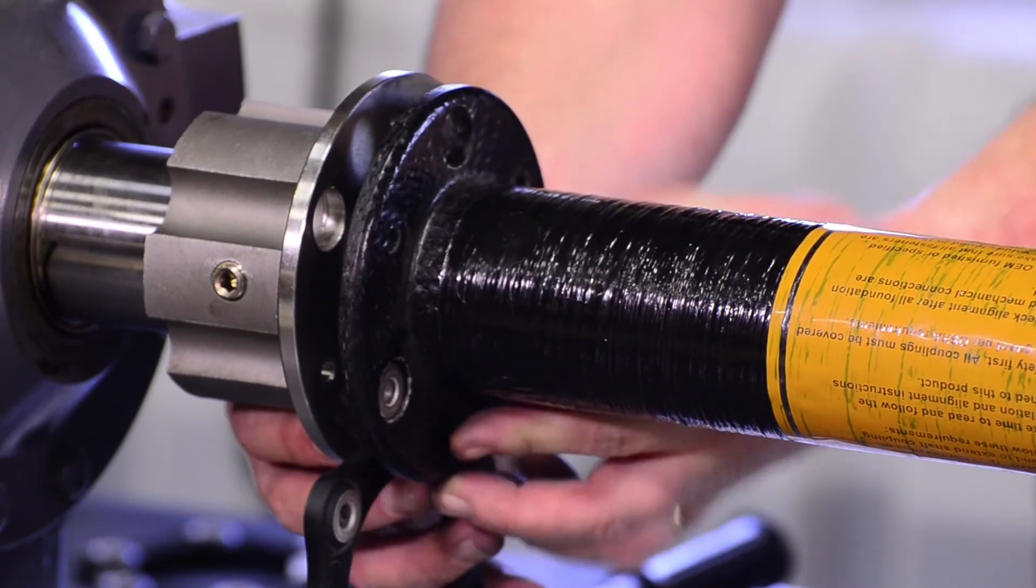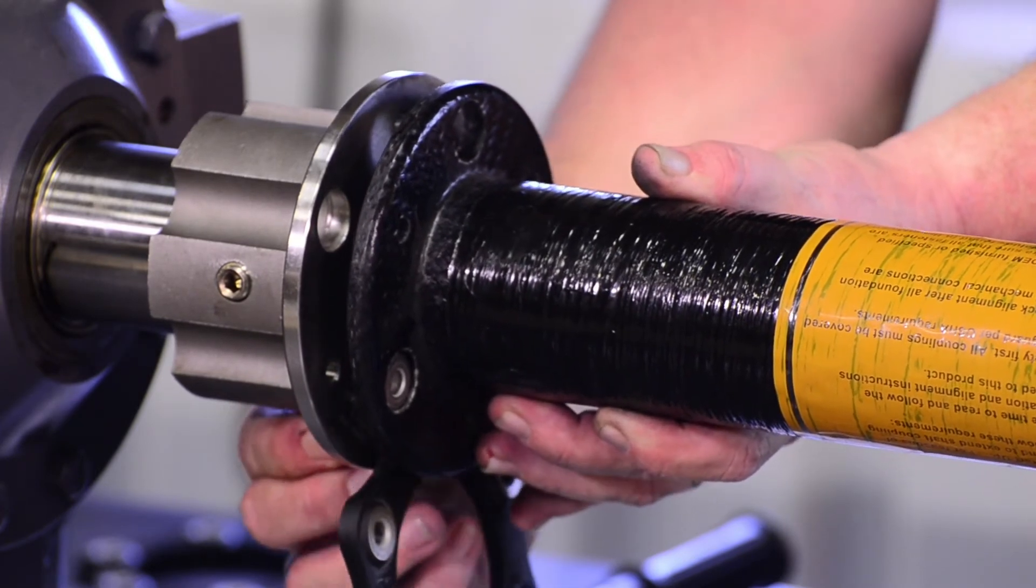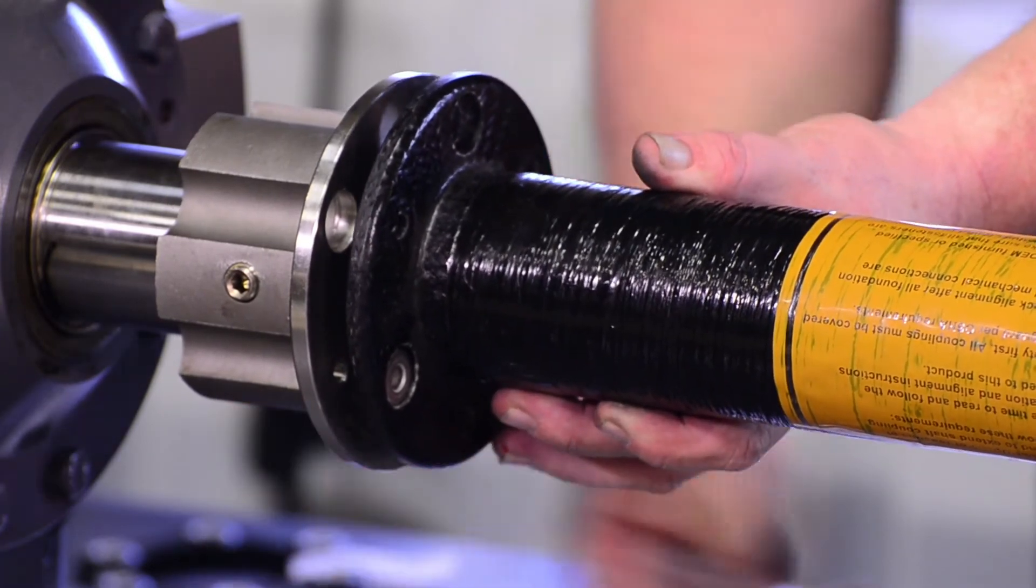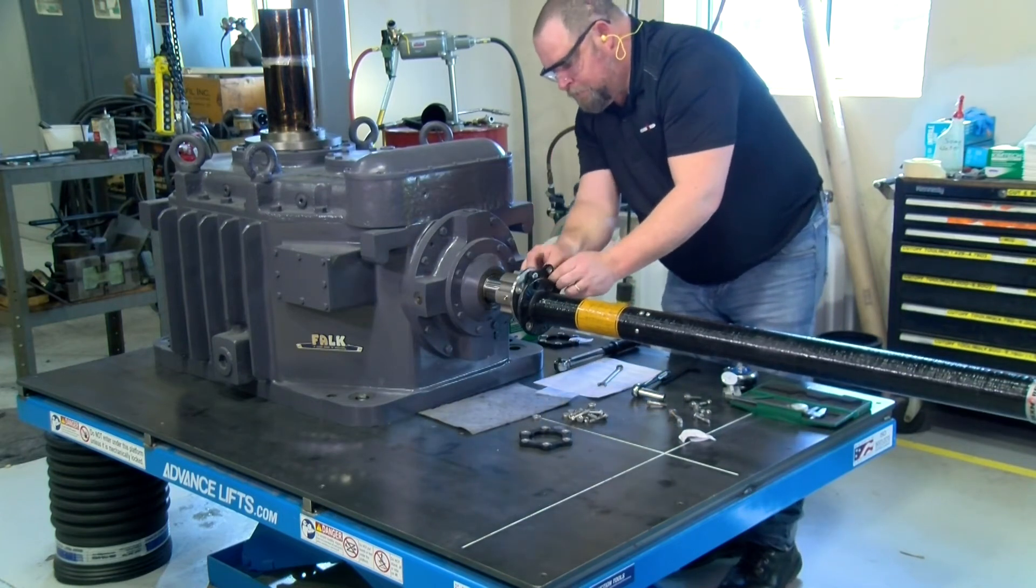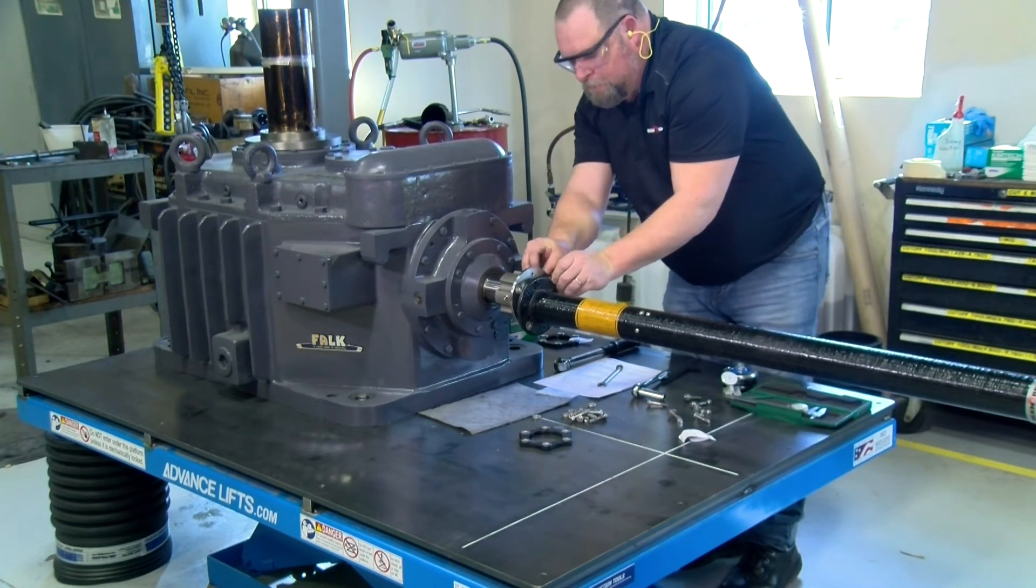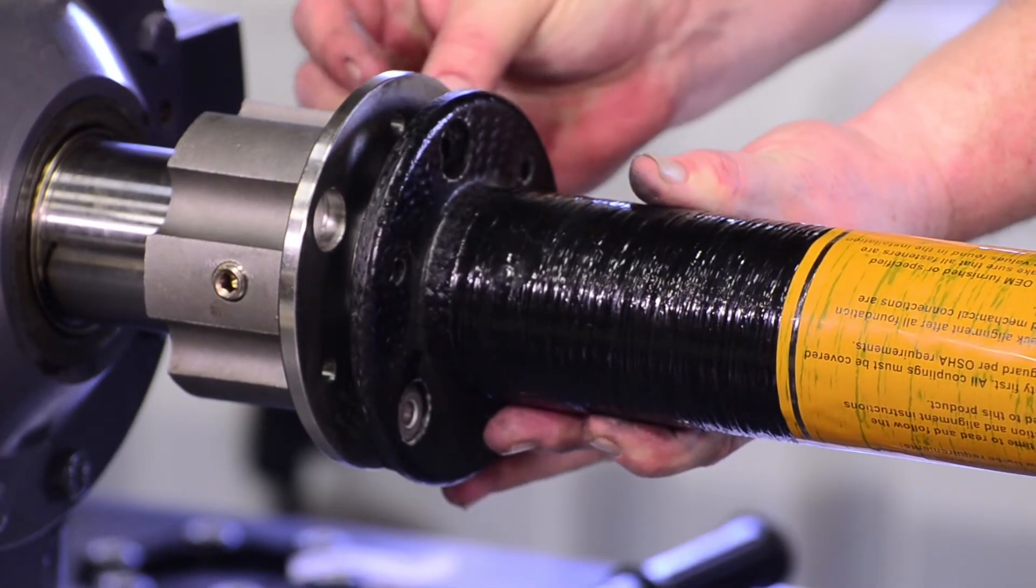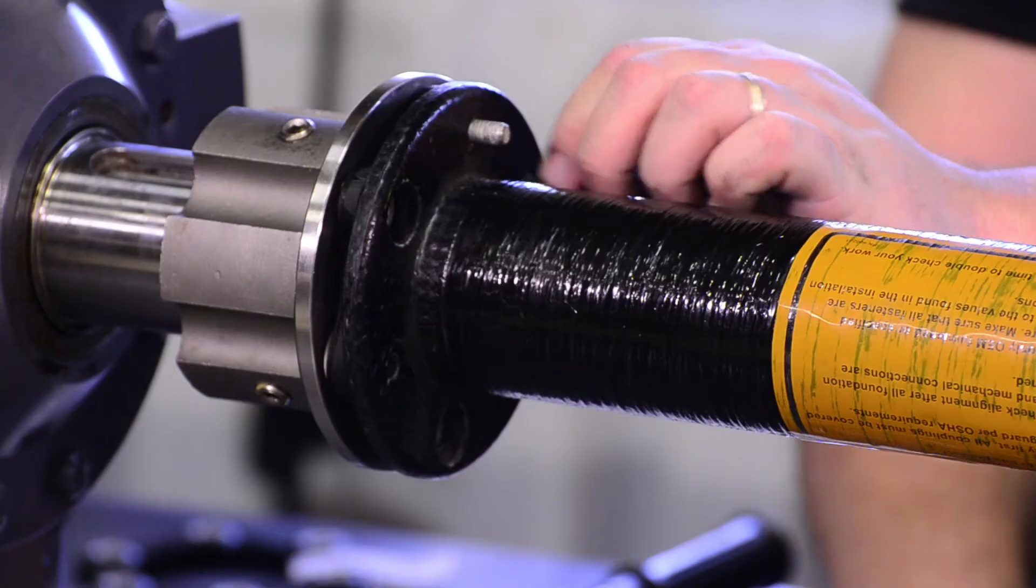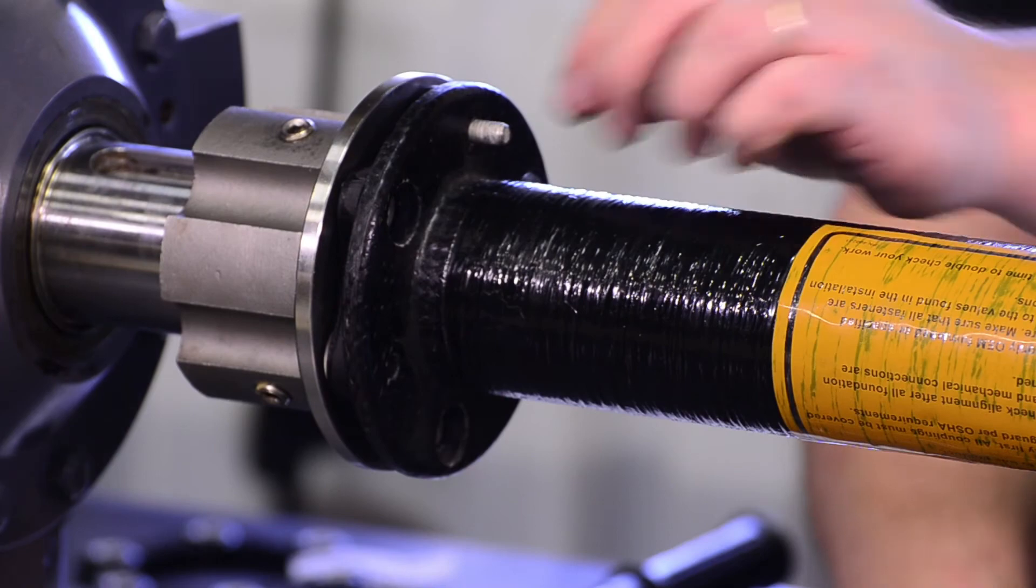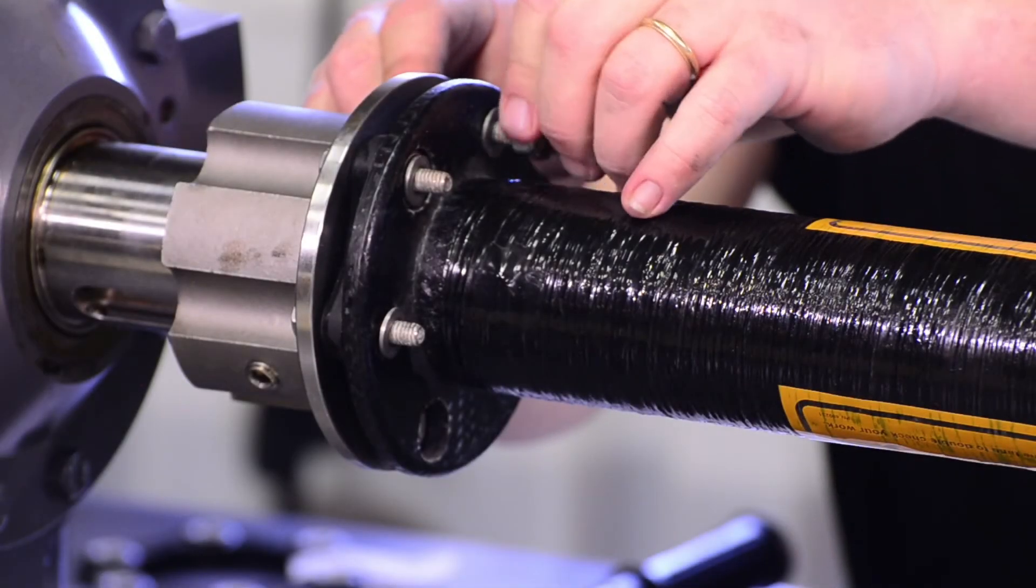Replace the flex element and hardware with new components. With the through holes of the new flex element aligned with the spacer and hub bolt holes, begin by inserting bolt and bushings through the large hole on the hub and through the spacer. On the other end, slide the washer over the bolt and loosely thread on the lock nut.